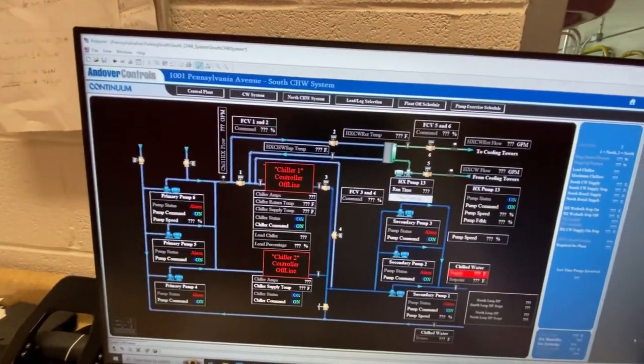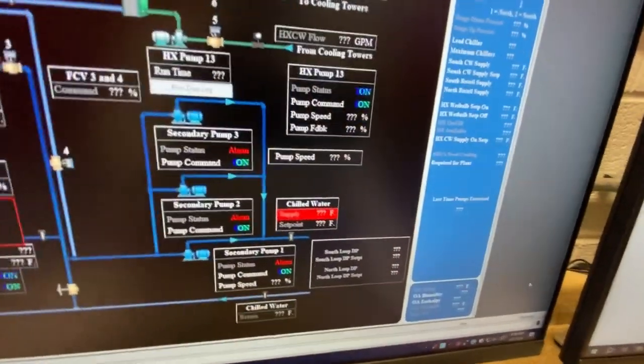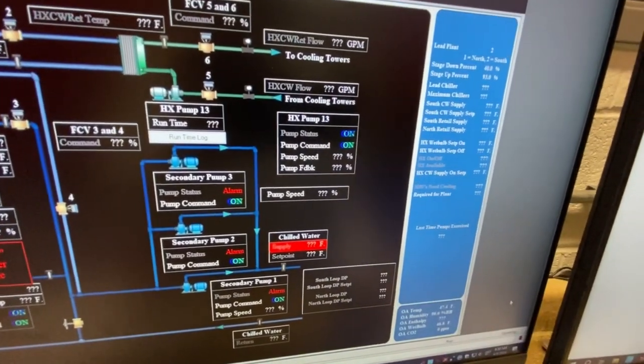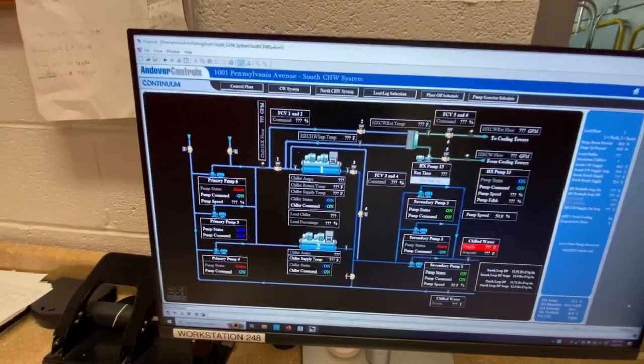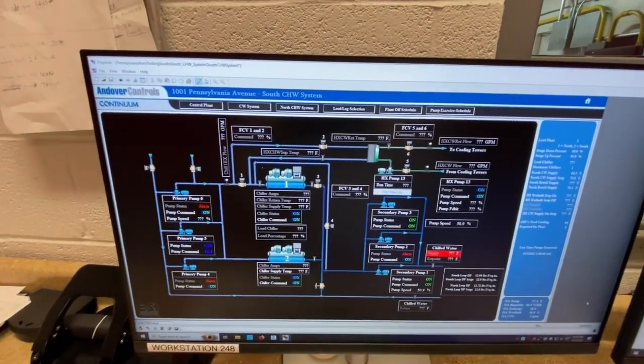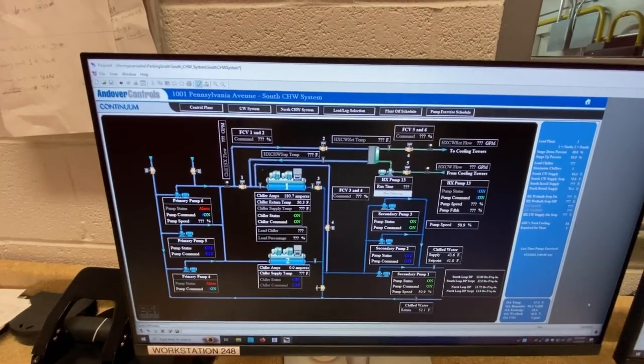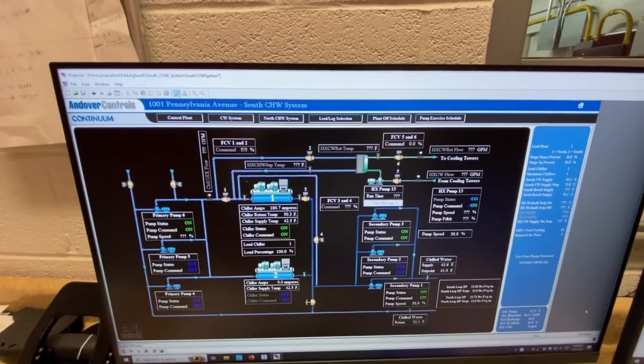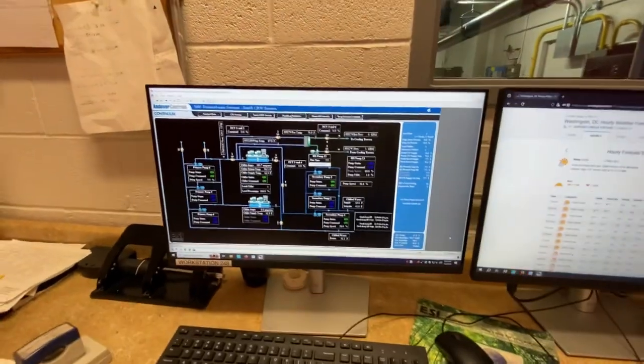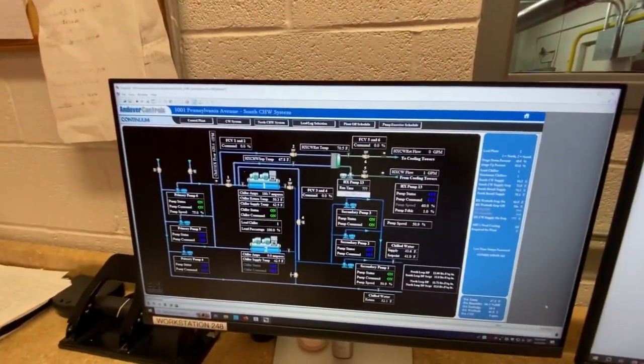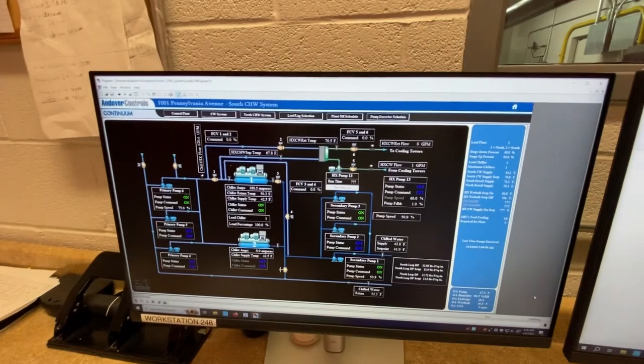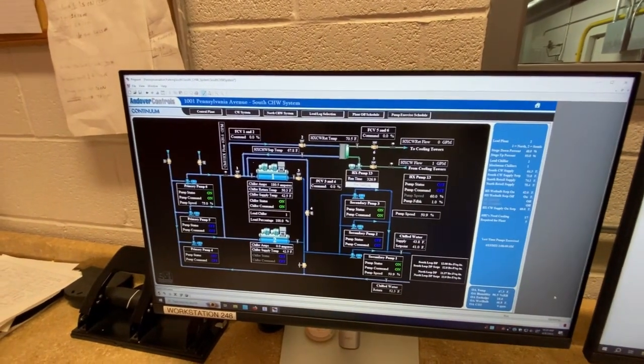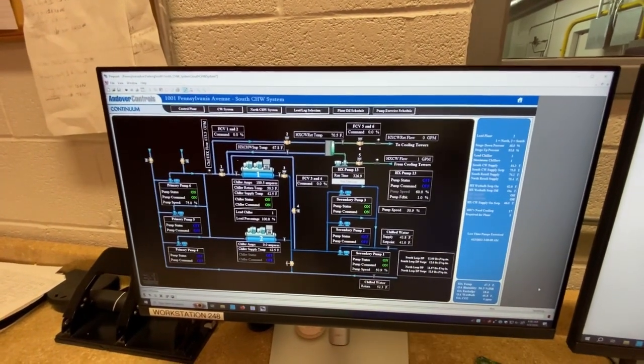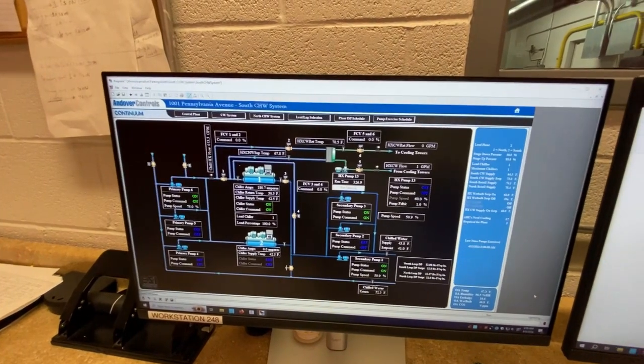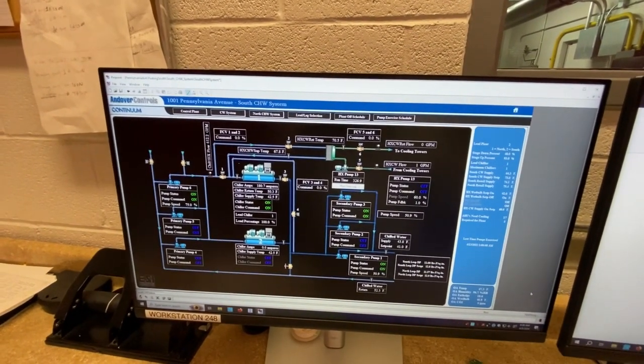South. The reason I'm coming back here is that this also shows you how many air handler units are on right now. The air handler units are the units on the floors, and we have them staggered. Some start at 6, some at 6:30, 7 o'clock, 7:30, and I think the last few sets come in at 8 o'clock. You don't want all your air handler units coming on at the same time. If you do, you're going to have an issue with your kWh, because you're going to have a peak. You don't want to set the peak too high, because that's how much you're going to be billed for on your electricity bill, based on the ratings.